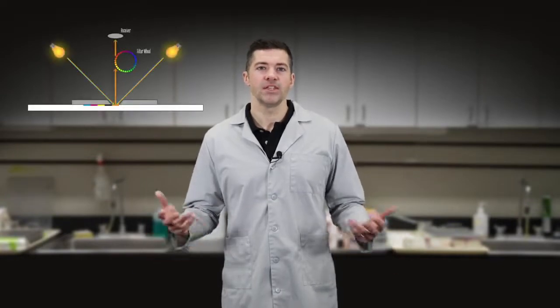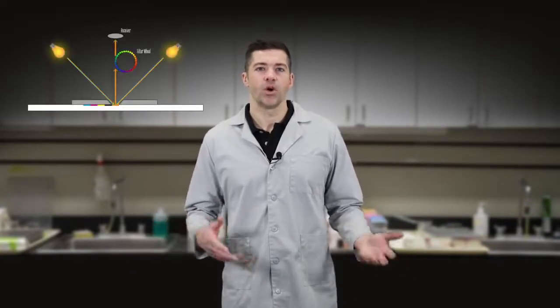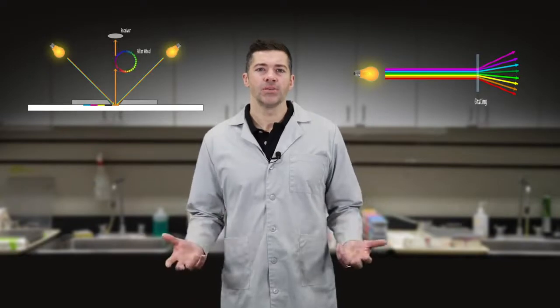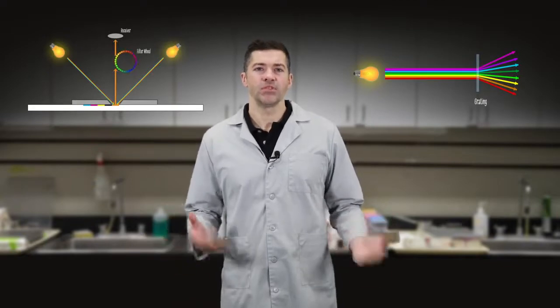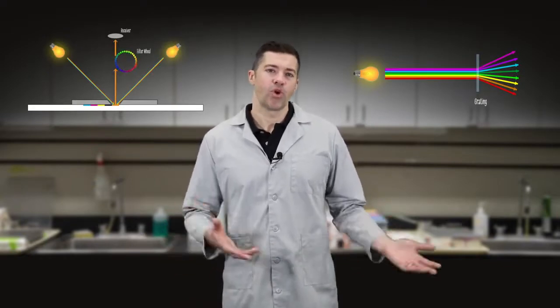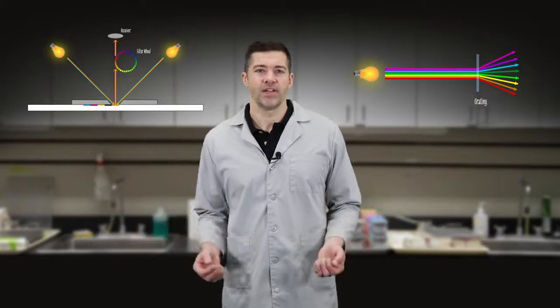This is typically achieved within an instrument using a spinning filter wheel of specially designed colors or diffraction grating. The resulting measurement is the sample's reflectance curve with a varying wavelength from around 400 to 700 nanometers. From this, we can compare the curves of two samples to see if they are a match.